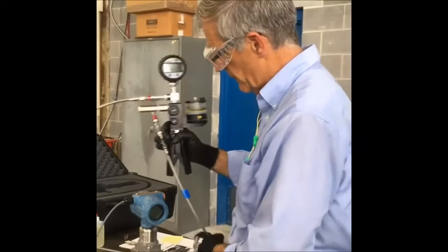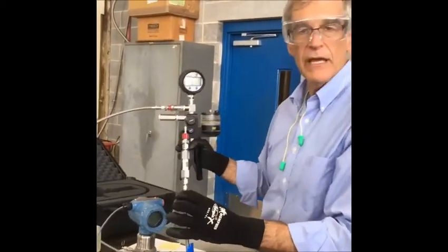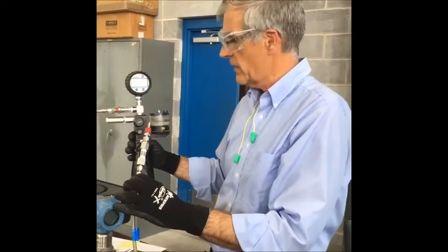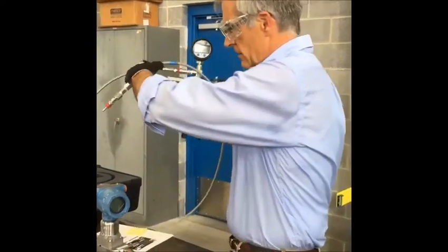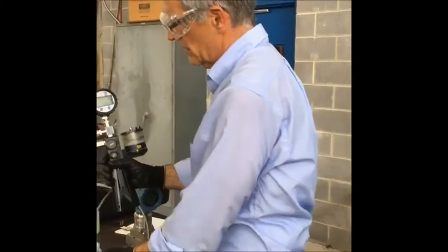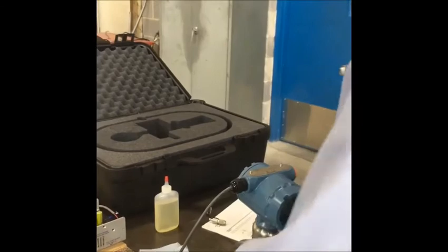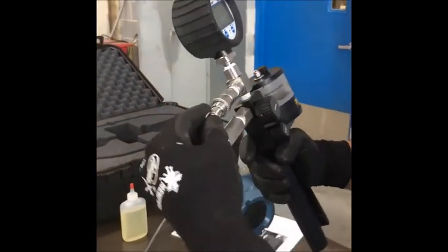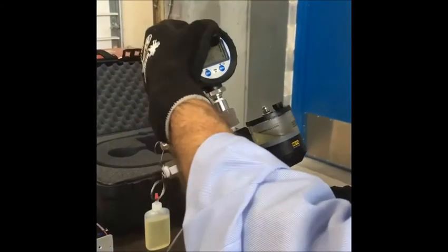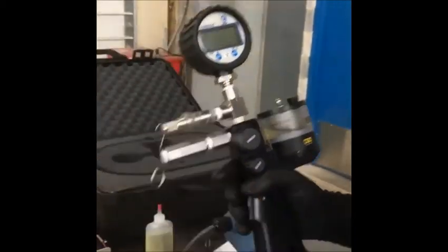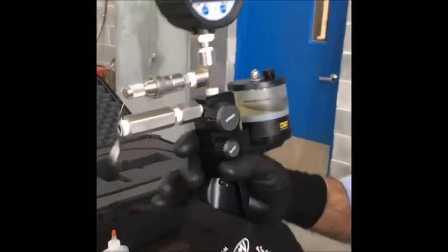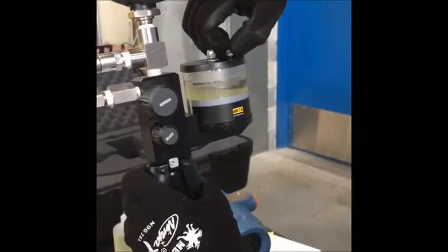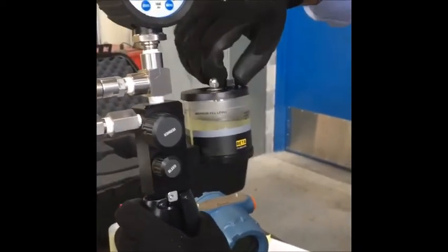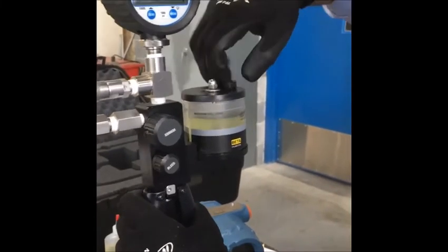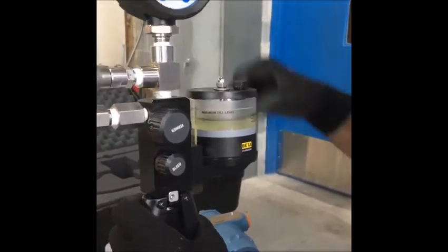And if I'm doing a series of calibrations, I could take this just the way it is and go on to the next machine and calibrate the next machine. If I'm done for the day, then I can remove the quick connect here at the pump, like that, and put my protective plugs back in, turn off the gauge, and we're ready to store it. Now, you might want to drain the oil out. This can get a little messy if the oil drains out in the carrying case, so you can drain the oil out into a suitable container if you're going to be storing it for a while.